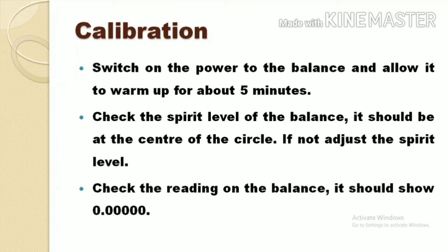Calibration. Switch on the power to the balance and allow it to warm up for about 5 minutes. Check the spirit level of the balance. It should be at the center of the circle. If not, adjust the level. Check the reading on the balance. It should show 0.000.